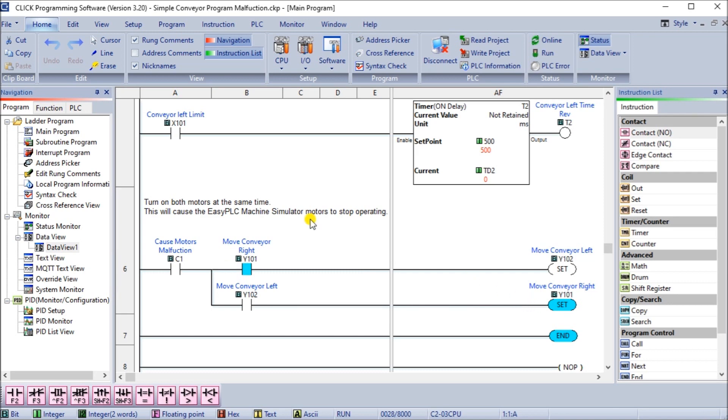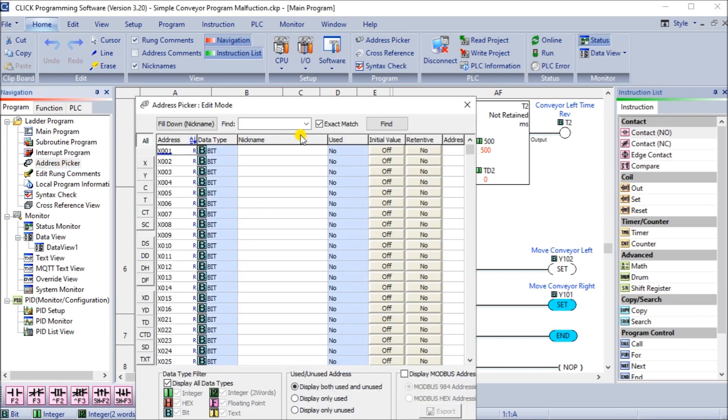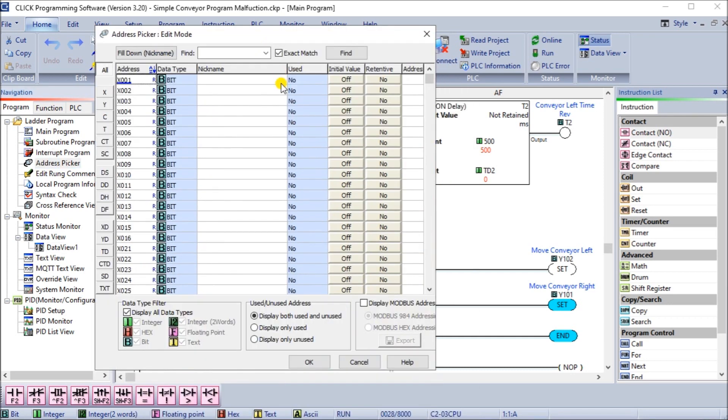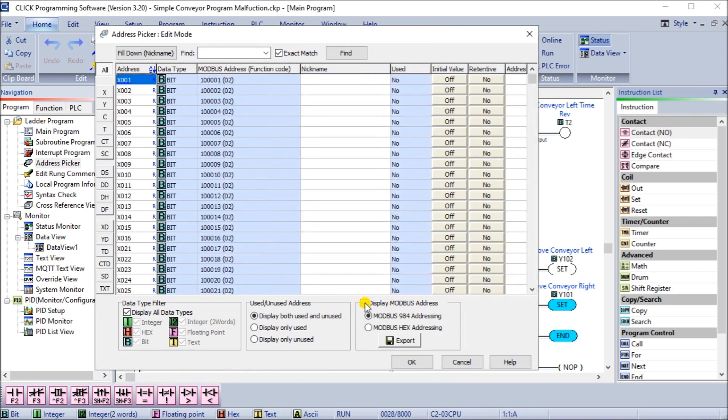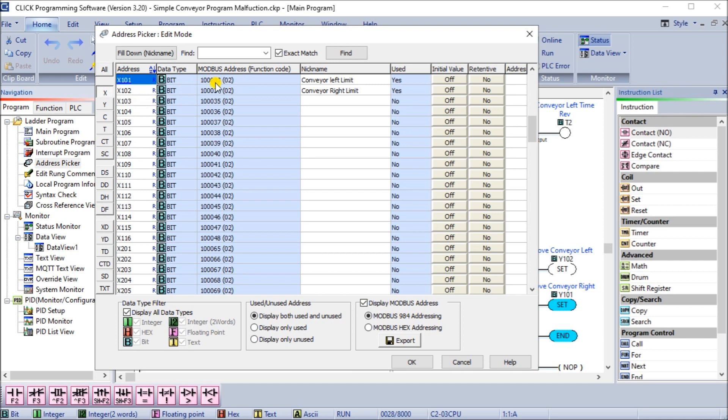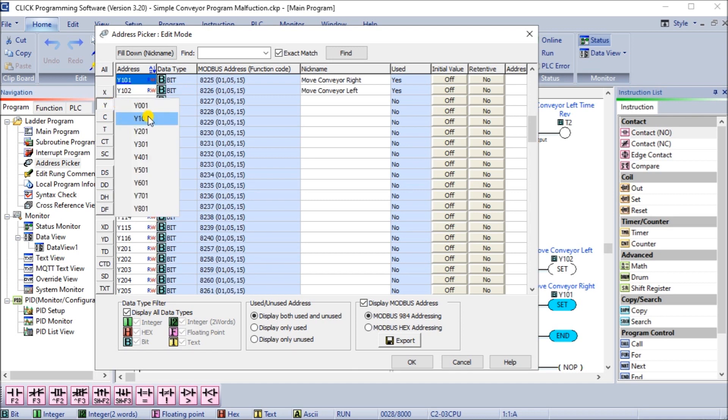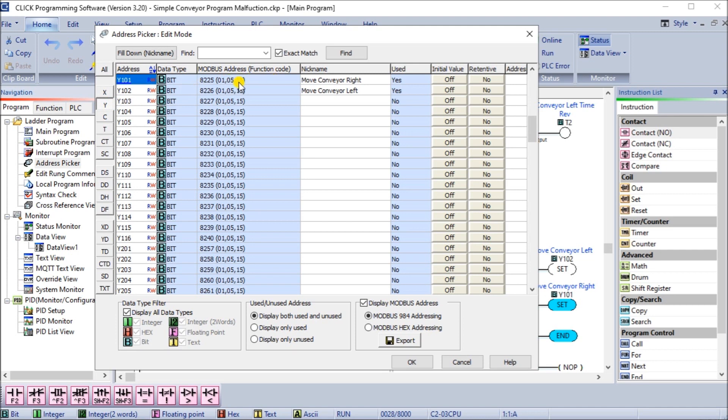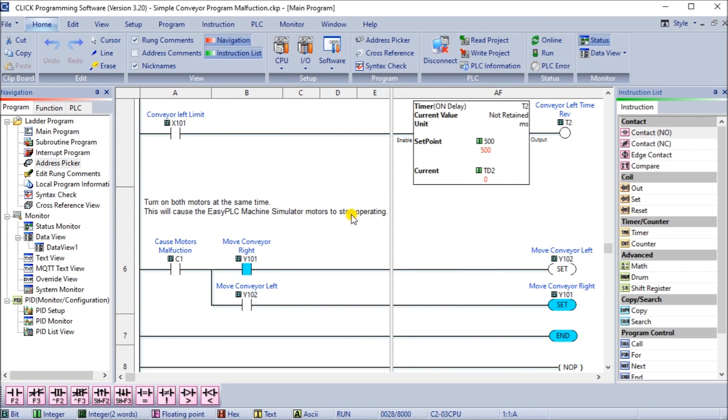Another couple of things that we need to do is determine what addresses so that our machine simulator can control these IO. If we go to the address picker, we will turn on display for Modbus addresses, because we'll be communicating Modbus. For our X, we're going to X101, which starts at Modbus address 33 and 34. So 33 and 34 will be our Modbus sensors. Our outputs Y, Y101 and Y102 will be address 8225 and 8226. We set okay. Those are the ones that we need to notice for our machine simulator.